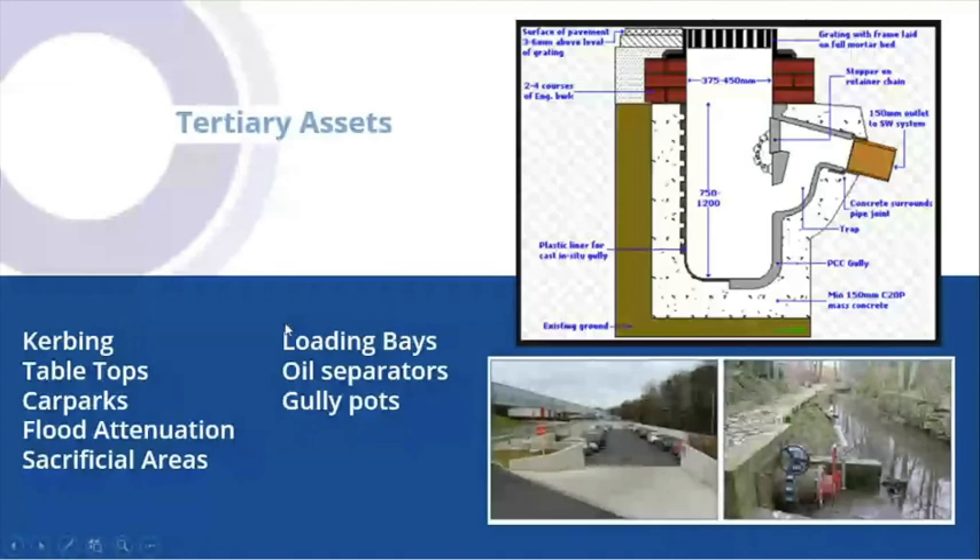Loading bays are perfect as existing assets. We visited a site recently where the loading bay is actually being flooded because someone put a valve system in and made the decision to close the drainage permanently — so it's always full. In my view this has surcharged the drainage. The pH monitoring isn't balancing, probably because of stagnant water. My bigger concern is that if I'm forcing drainage to be constantly flooded, I'm potentially pushing water to find another route off site and potentially undermining my foundations.